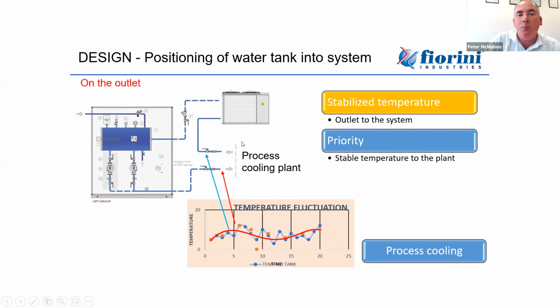positioning, I should say, is where you put the buffer tank on the outlet of your chiller. So here, where we might have the compressor cycling on and off and slight variations in temperature here, the buffer tank is gonna stabilize that temperature and you get a very stable temperature going to the process, to the plant. Now, more often than not, you don't need it, but very, very precise.